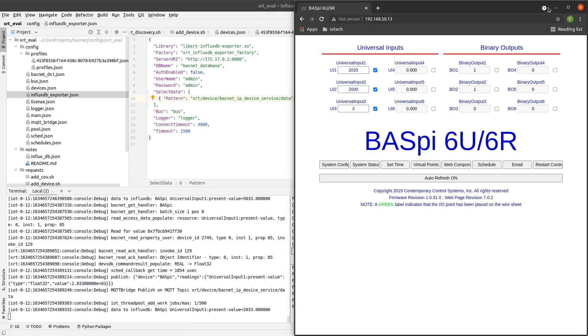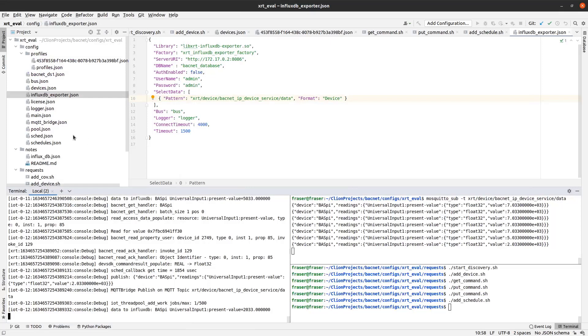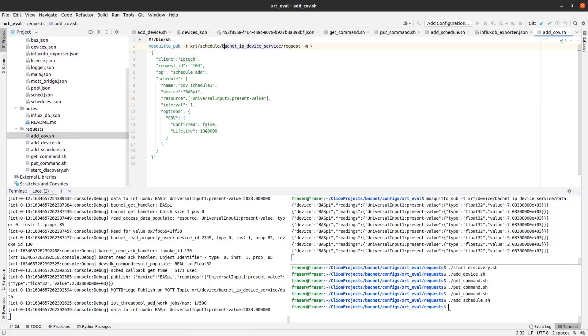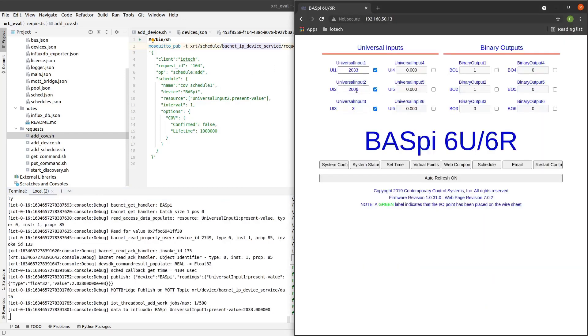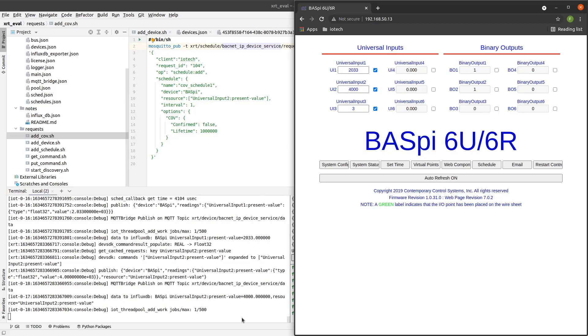For the final step in the demo, I will configure the XRT BACnet device service to support change of value, or COV, on Universal Input 2. You can see the JSON payload for this request. I will then send the request to configure Universal Input 2 with COV support from the second console. The value of Universal Input 2 will only be read and published in InfluxDB if it changes. You can update its value in the BASPi device console, the COV will be triggered, and you can see the updated value displayed on the Grafana dashboard.